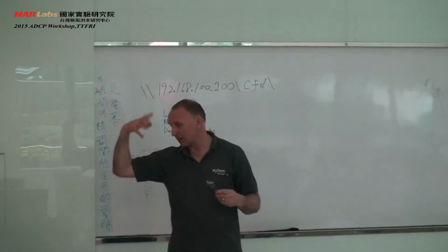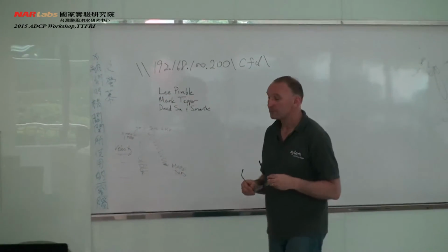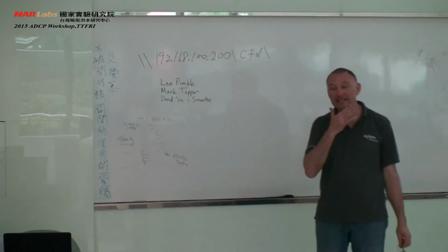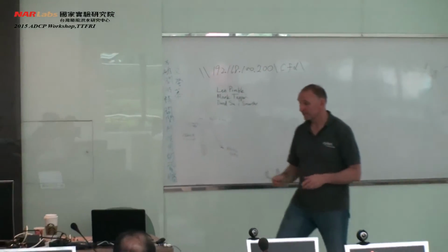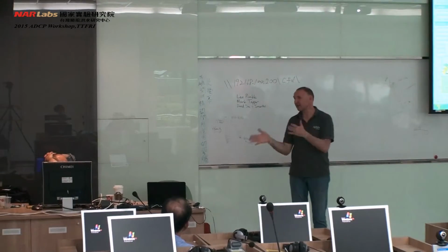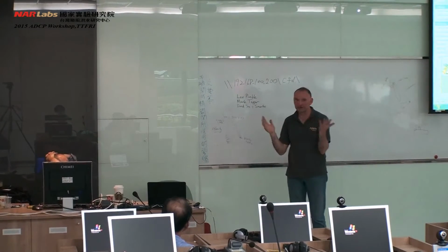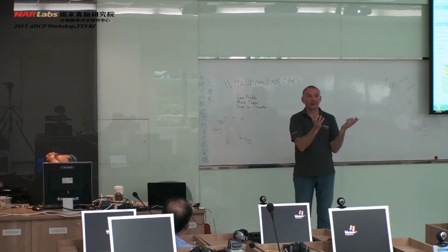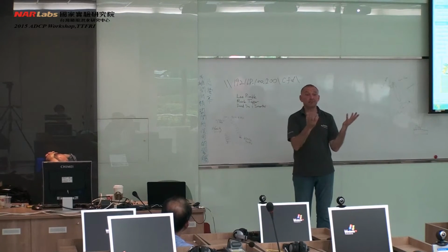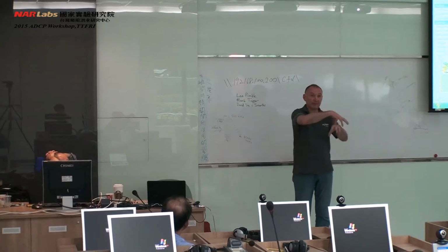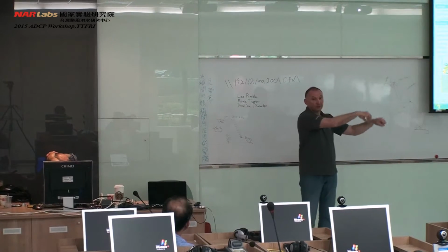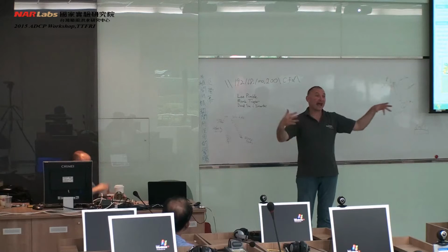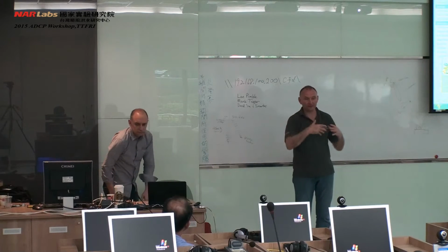If they all have to use the same transducer, that slows it down. Actually, that doesn't matter, because it still interleaves the pulses. It does slow down slightly, but it's not to the degree that we should worry about. Okay, it's roughly pinging 70, 80 pulses per second, but it depends as to whether it's using 3 megahertz, 1 megahertz, whatever, as to how it allocates all of those pings.